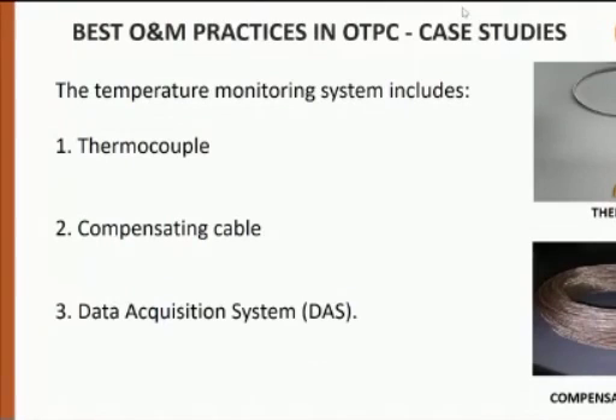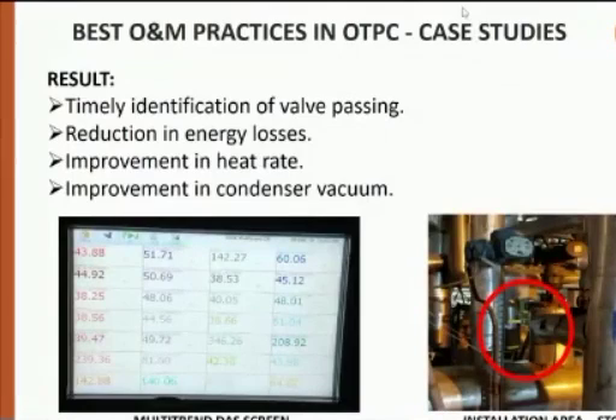So this is the figurative presentation of the thermocouples which were installed on the valves, and the temperatures being captured in the data acquisition system. After installation of this system, we got very good benefit. First, we can identify which valves are passing. Second, the energy loss is also reduced. Heat rate improved, and there was an improvement in the condenser vacuum. So this was one improvement done by the plant operation and maintenance team, which has given very good results in improving the heat rate of the plant.